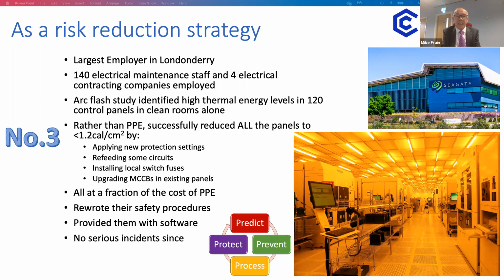But there lies the answer to reducing the risk. If they can do it there, why can't any industrial site do the same? And of course, I've got a good history over the years of doing exactly that. Retrofitting circuit breakers, or tuning them down and whatever to reduce the amount of incident energy. Wrote their safety procedures and provided them with the software. Every time they replace what they call a tool in the fab, it was pointless me doing new calculations. I taught them how to do that all themselves, and there've been no serious incidents since.